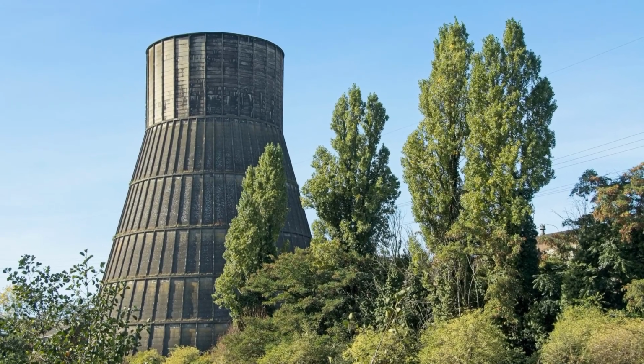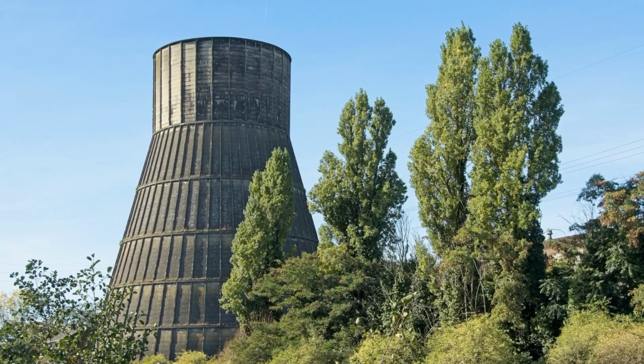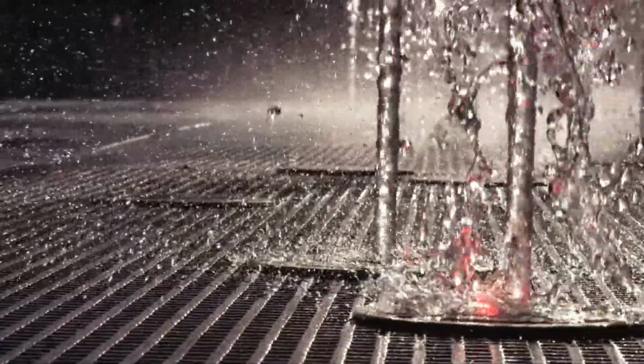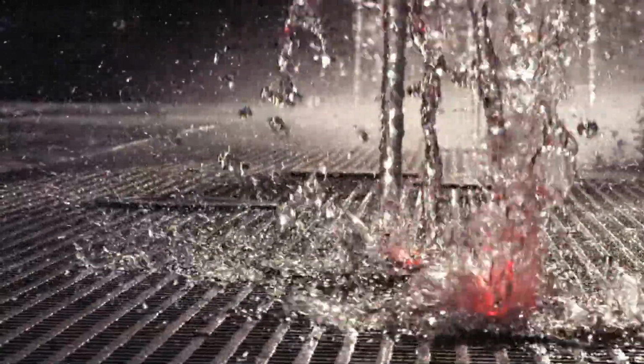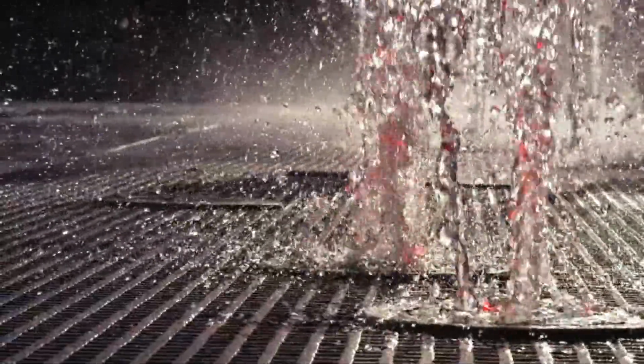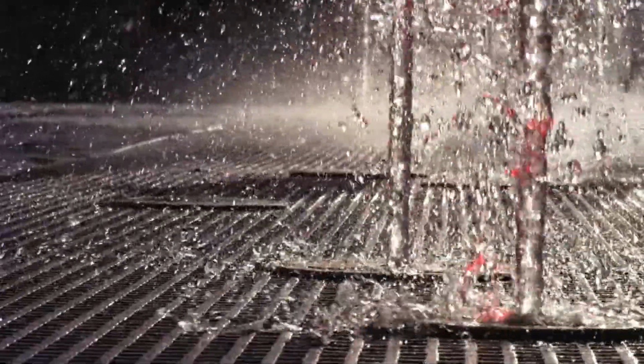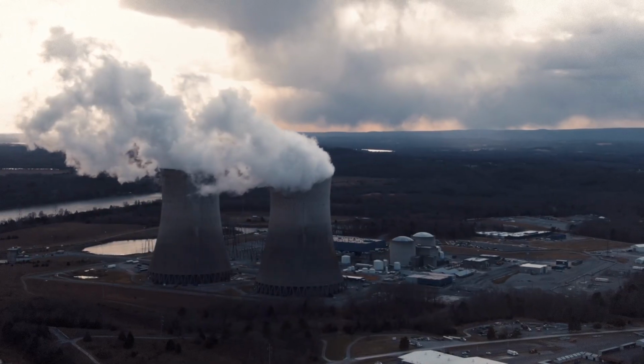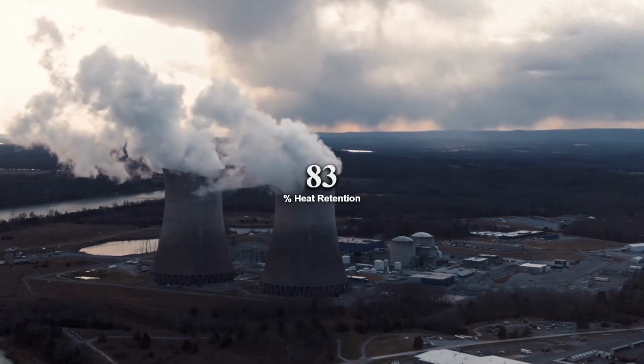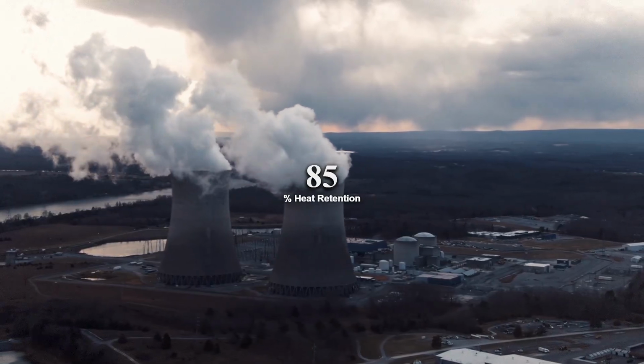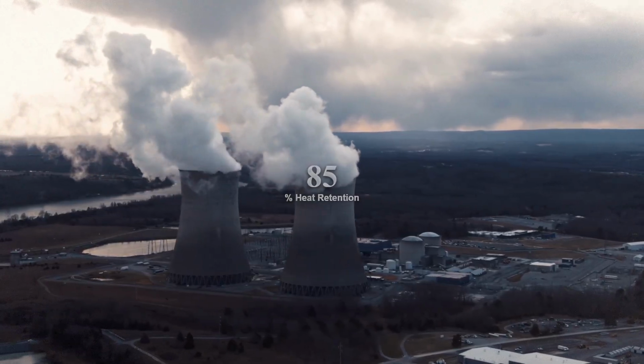Even after solving airflow issues, engineers faced another challenge. The water inside the towers was not cooling efficiently enough. Large streams of hot water fell like waterfalls from the upper sections of the structure. The droplets were so large that they could not release heat effectively to the passing air. Many reached the bottom while still carrying significant amounts of heat, reducing the efficiency of the power plant.